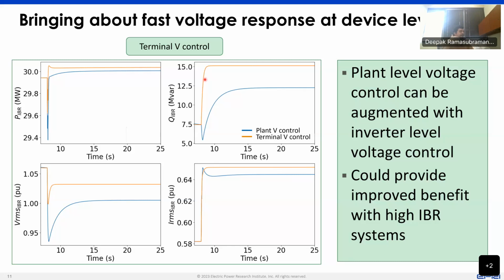So by transferring some of this control to the inverter level, we don't mean to say that the control at the plant level has to vanish. We still need that plant level control because we still need control at the point of interconnection, which could sometimes be a few kilometers away. So then you need coordination between your plant level control and the inverter level control, which does make it more challenging.